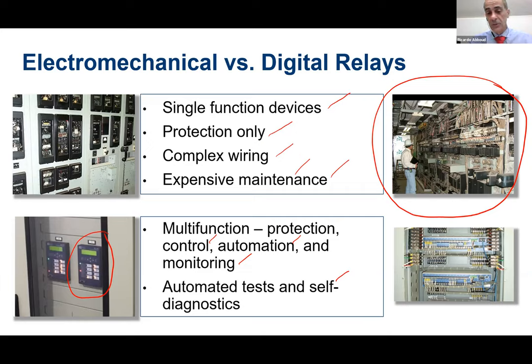In the case of the digital relay, we have the self-diagnostics. So this will alert you when there is an internal problem in the relay. And also with the digital relays, we can have automated tests. That means if you have a modern test device, you can perform some automated tests that will make the maintenance much shorter in terms of time. Okay.